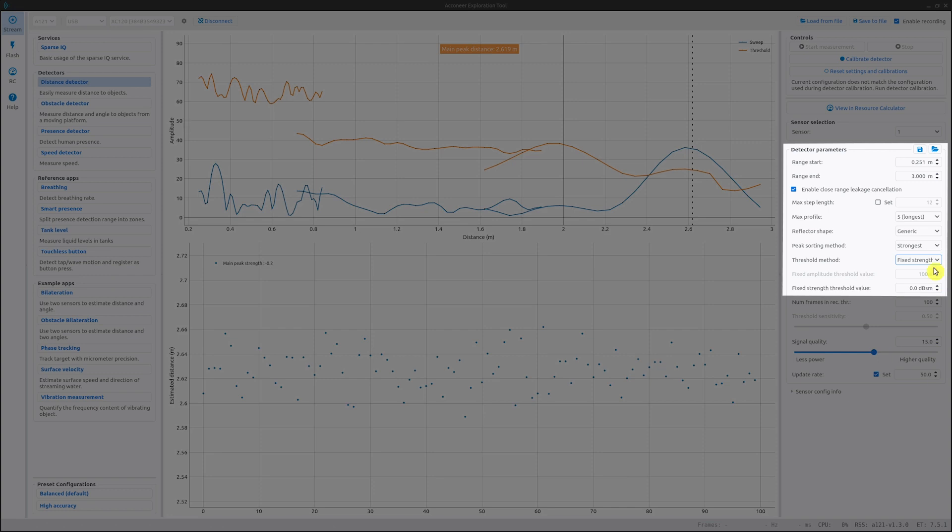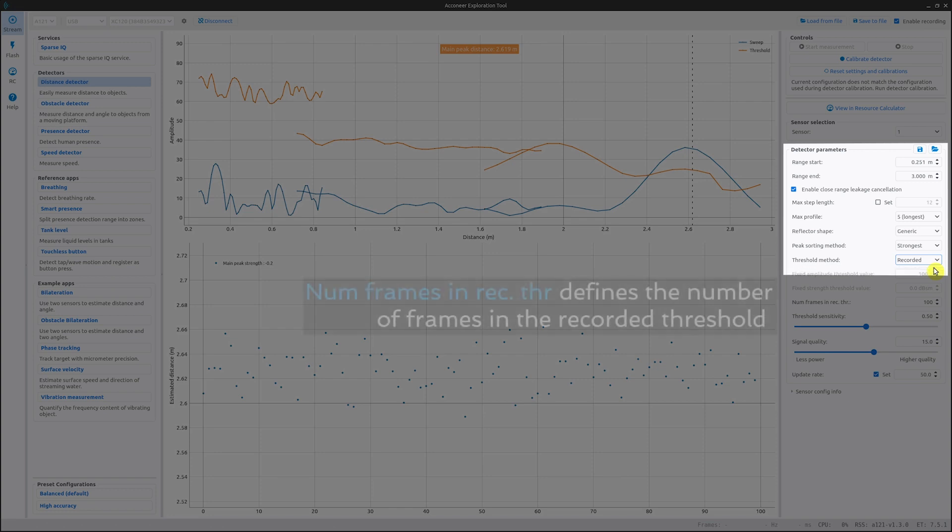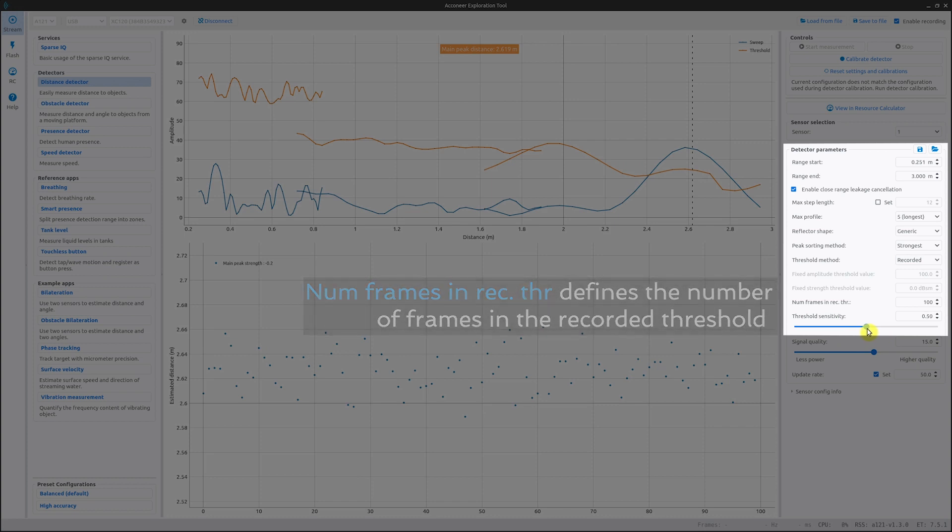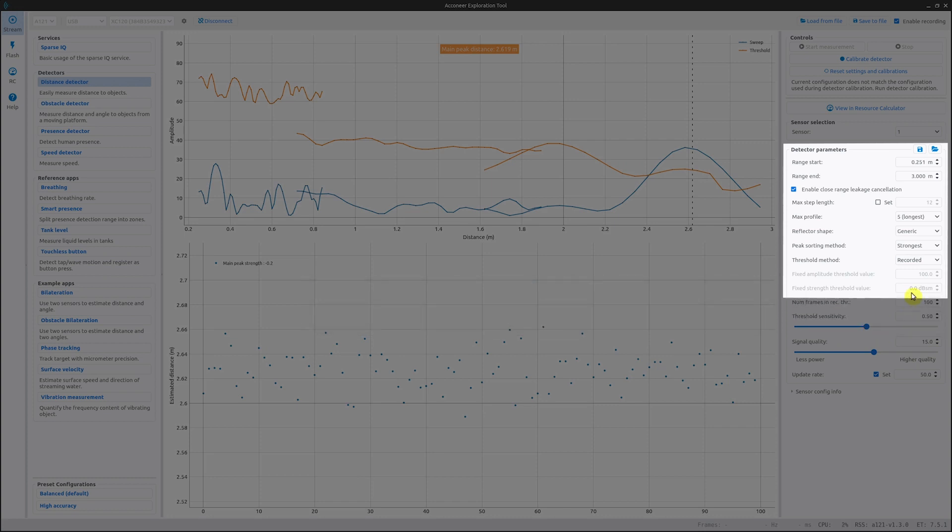Our next option is the recorded threshold. In situations where stationary objects are present, the background signal is not flat. To isolate objects of interest, the threshold is based on measurements of the static environment. The sensitivity of the threshold is adjusted by the threshold sensitivity setting, which is found below. The recorded threshold has a built-in temperature compensation based on the internal temperature sensor.